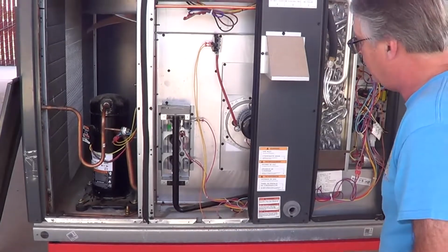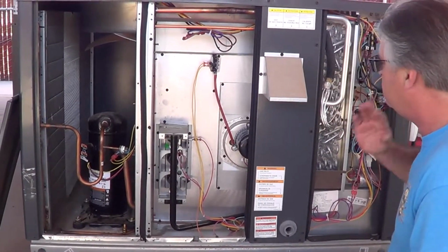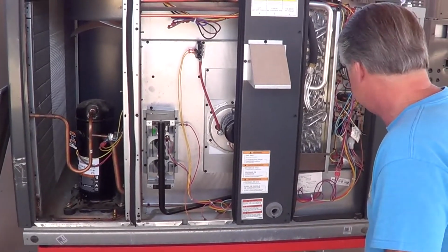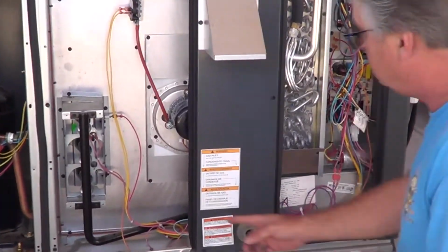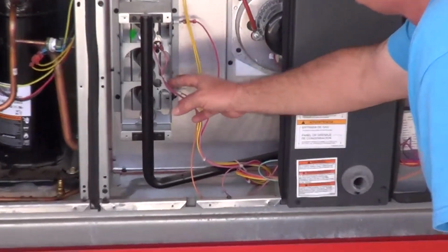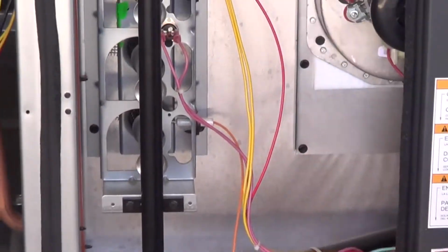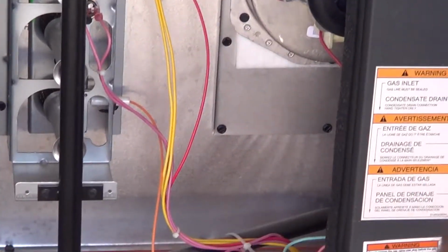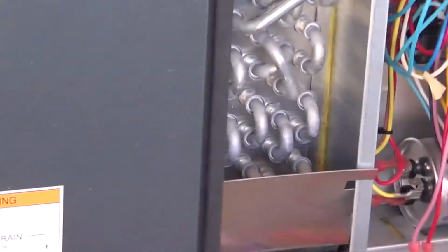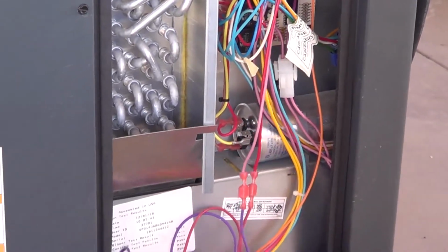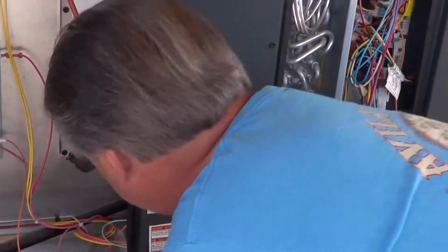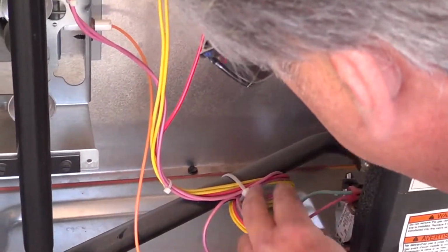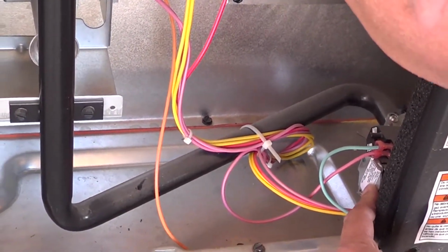After we've proven the inducer fan motor is operating, the next thing that happens in the sequence of operation is that high voltage is sent to the spark emitter, so we have the high voltage arc, and the next thing that is happening is the gas valve is then energized by the IFC. It sends power, I believe, through red and blue, or red and purple, or red and green, pink and green wires going to the gas valve here.